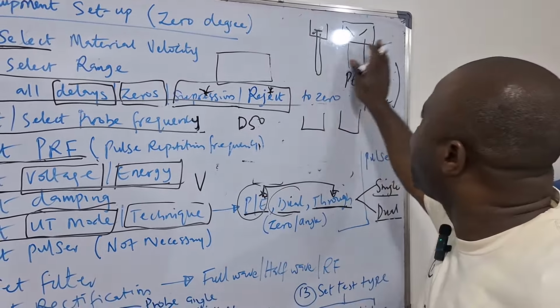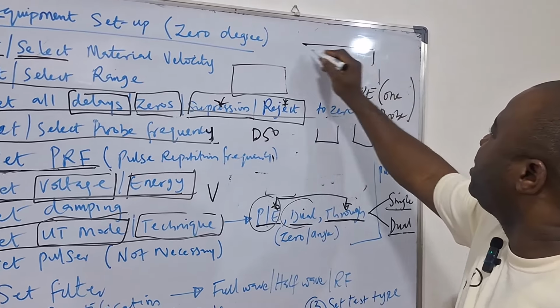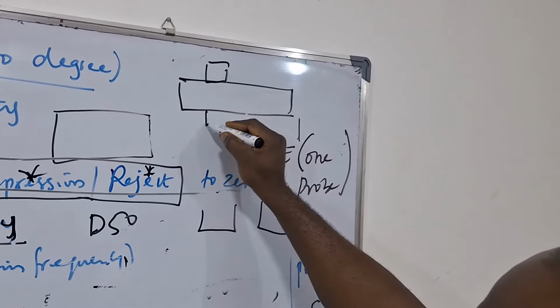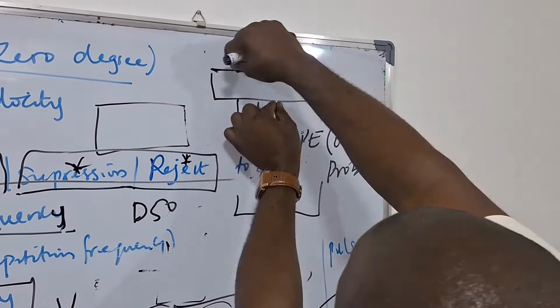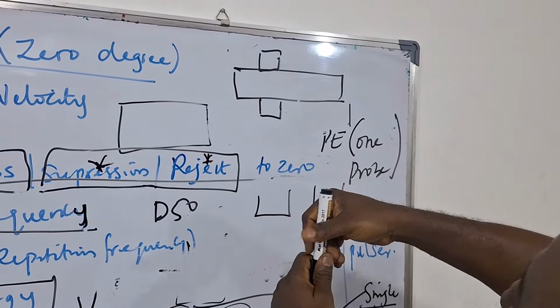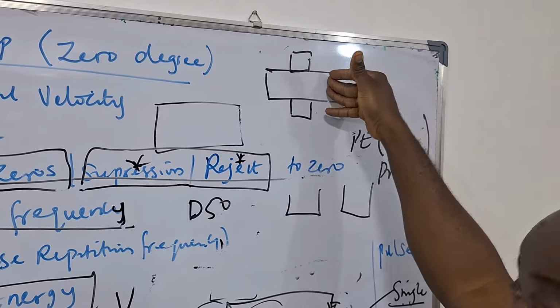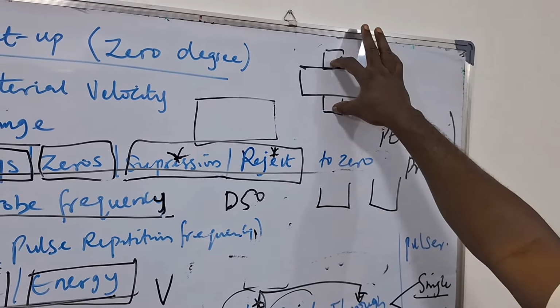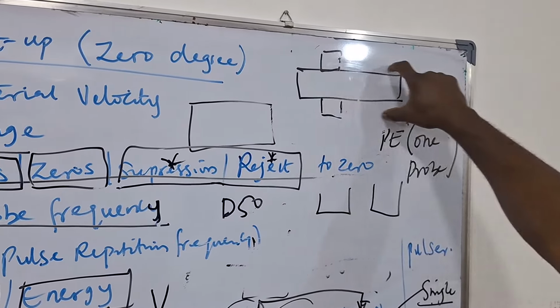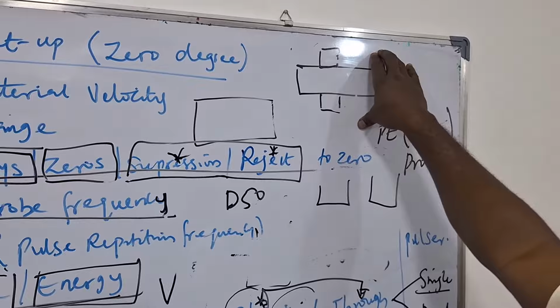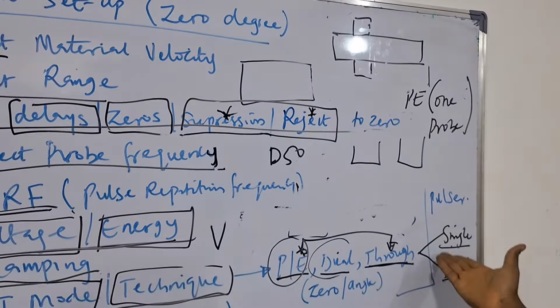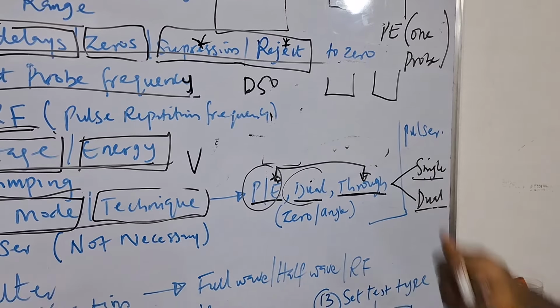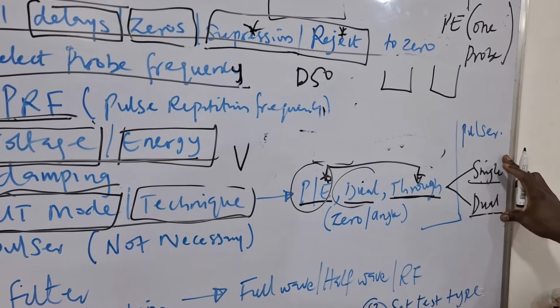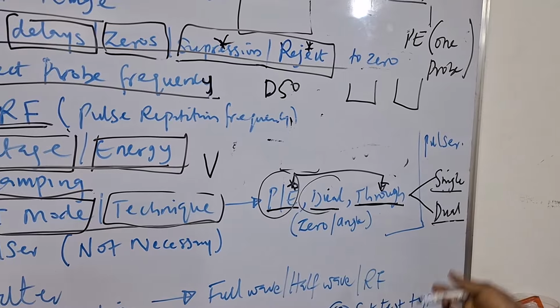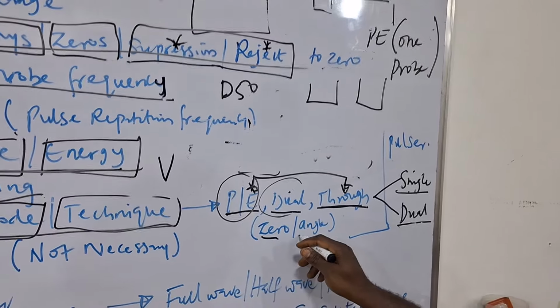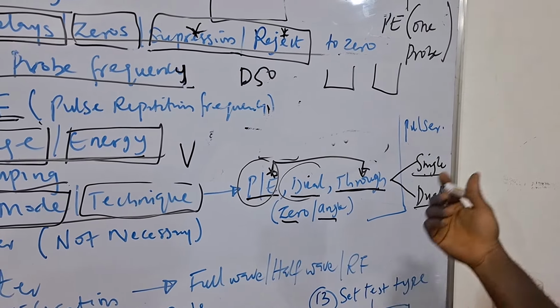Because if you are doing through transmission, for example, it means that if this is the material, one probe will be on top and the other probe will be at the bottom, and you are going to be moving them. Immediately you shift them out of alignment, it's no longer going to give you any reading or echo or whatever, because you have missed it. So for through transmission, you are going to jig this together and you begin to move them around. So that is a separate topic for another day. So you need to understand the whole concept of the technique you are dealing with. Some units will give you this option, some units will give you this. Know what you are doing and understand the concept. In some other cases, some will give you 0 or they will give you angle probe. But know what you are doing.